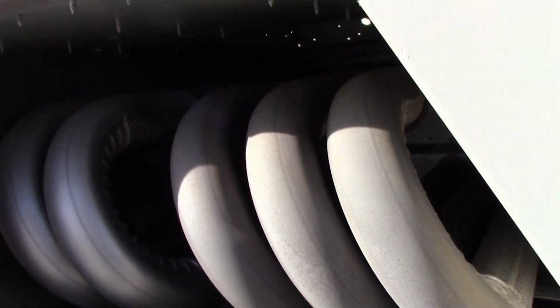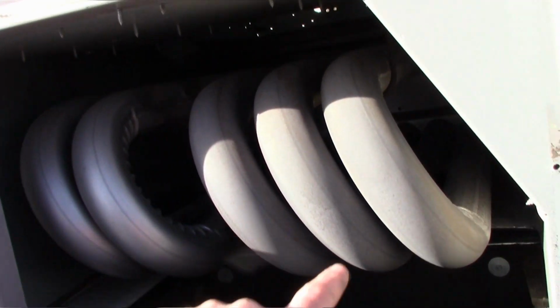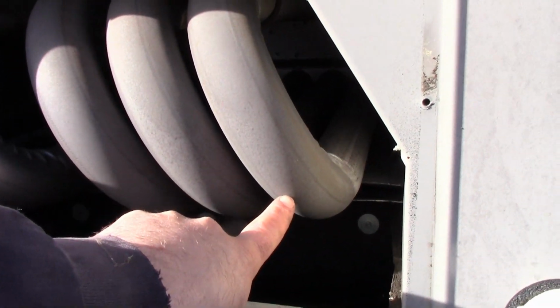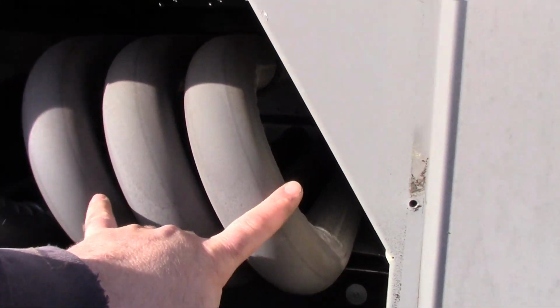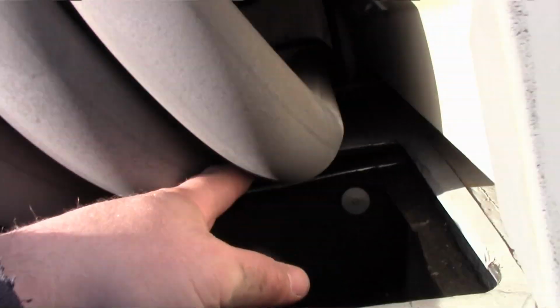Okay, so here's the heat exchanger coil bends. Usually on most Carriers, where they're going to break is going to be right here at the very bottom of the first set of burners, or split right along the seam that's on the side. And these are perfectly fine, so I can put that panel back on.